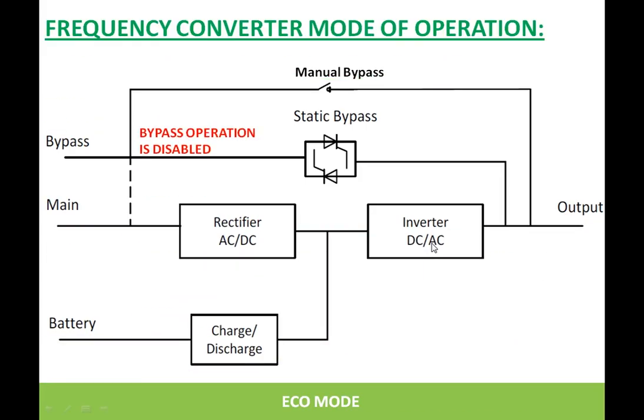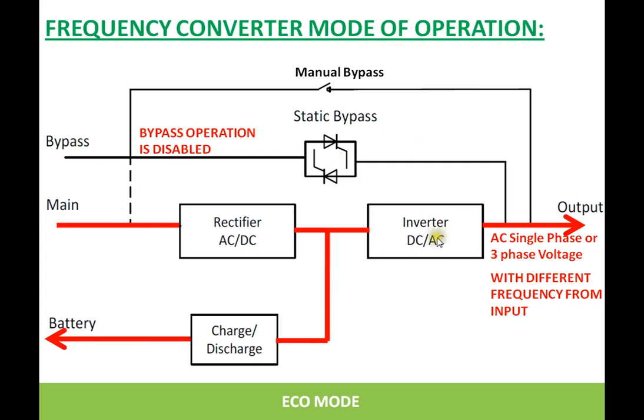The other mode is the frequency converter mode. This mode is used when the load requires a different frequency than the incoming mains frequency. For example, if the incoming mains is 50 Hz and the load requires 60 Hz, this mode can be used so that a different frequency is available at the UPS output. Under this mode, the bypass must be disabled because the load will not accept the incoming mains frequency.